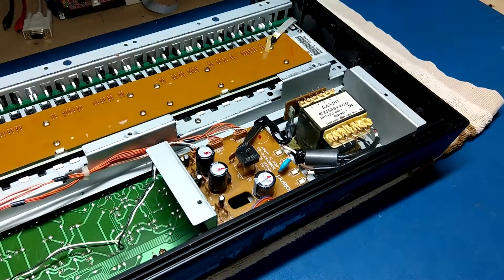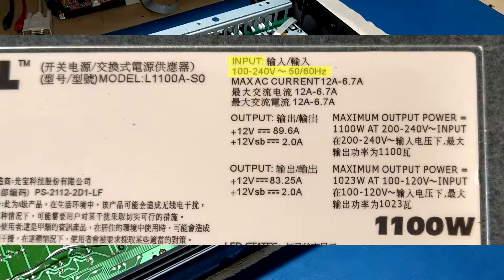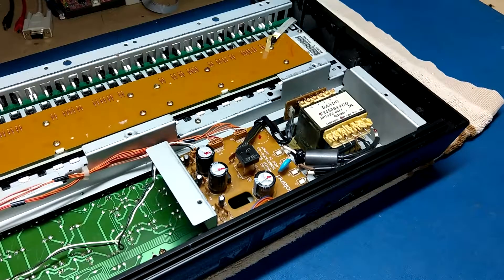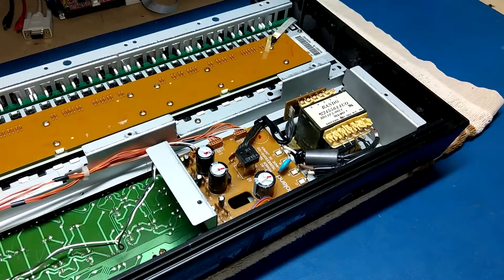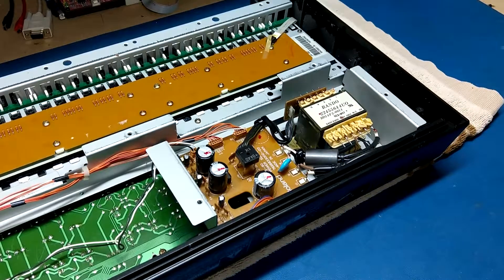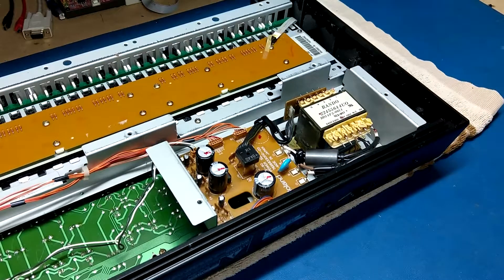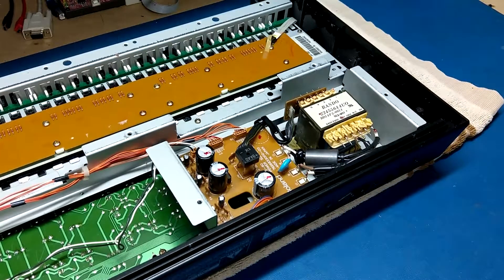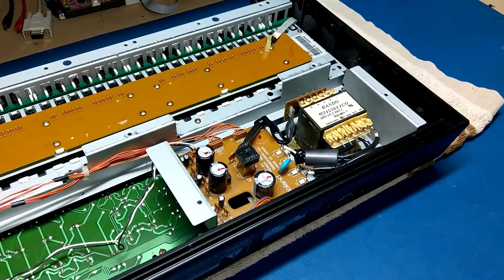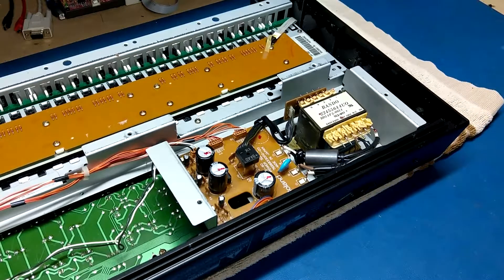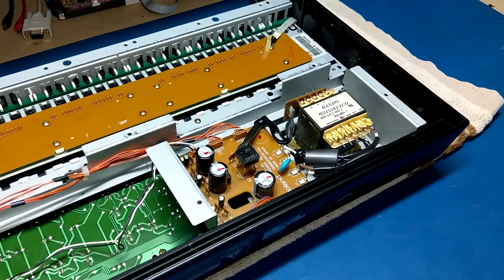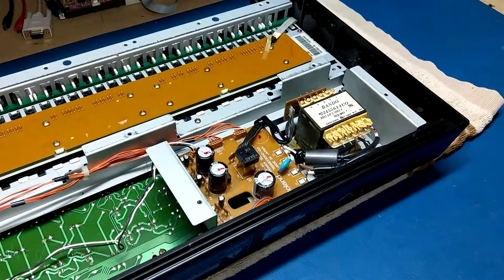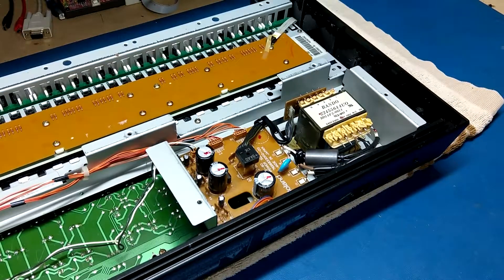With a lot of modern electronics, they use switching power supplies, which accept a very wide range of input voltages. They'll run basically anywhere from as low as 60, 70, 80 volts AC, all the way up until 240-250, sometimes as high as 300 volts AC. You see this in servers a lot, specifically because data centers run on a lot of different voltages. On three-phase power, 208 volts is very common, a lot of things still run on 120, 240 volts is also a possibility. So they make the servers run on a very wide range of input power. Typically the higher the voltage the server runs on, the more efficient it runs and the less heat it produces. The higher the voltage, the less current it uses.